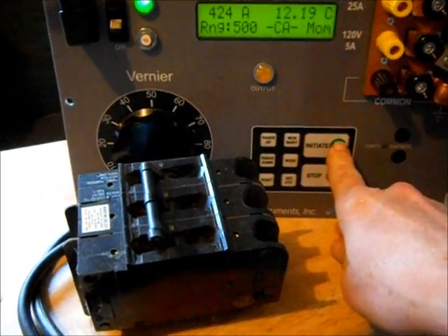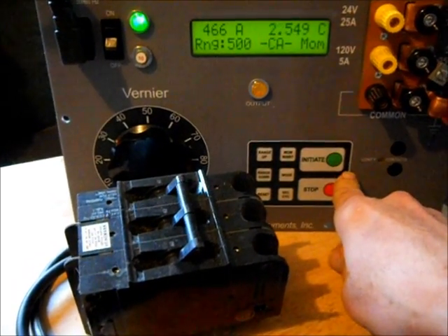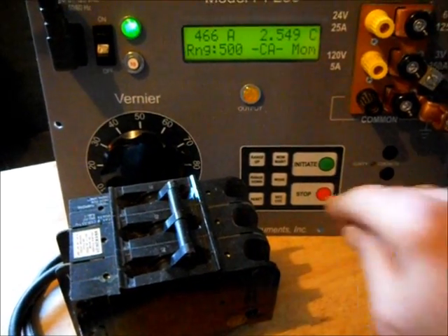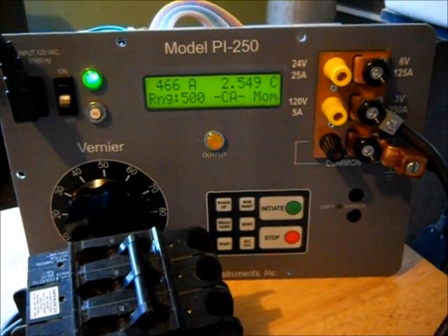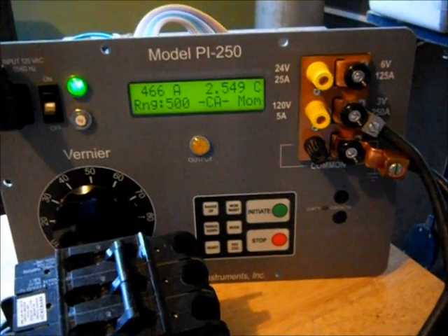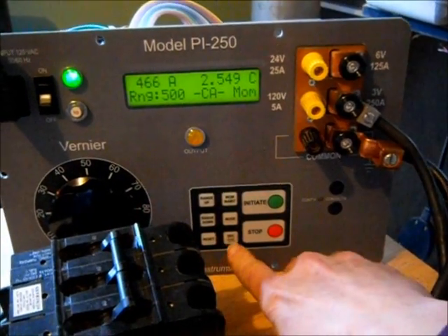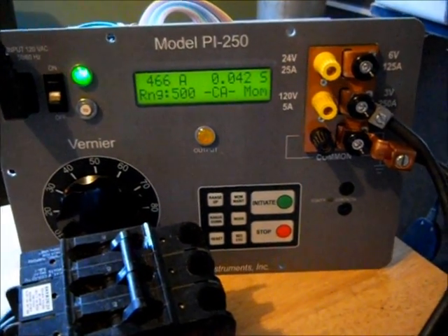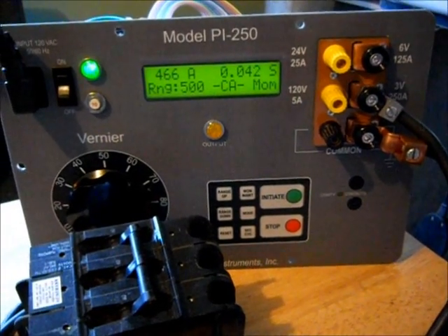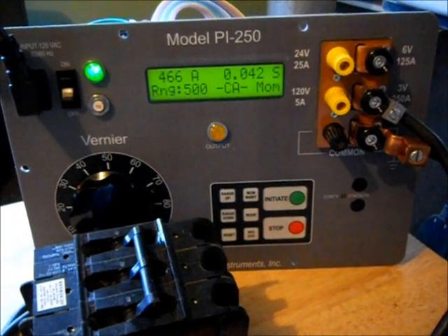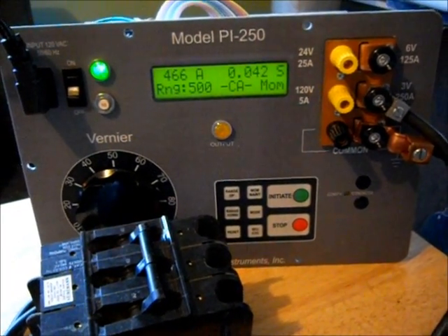Maximum. Okay, tripped at 466 amps, 2.5 cycles, or 0.042 seconds. All right, now we can try it for a time delay.